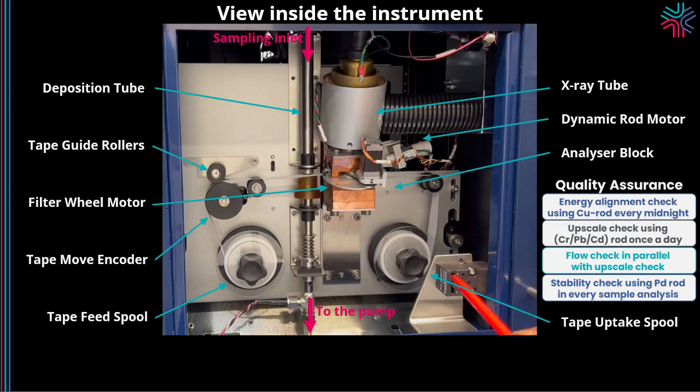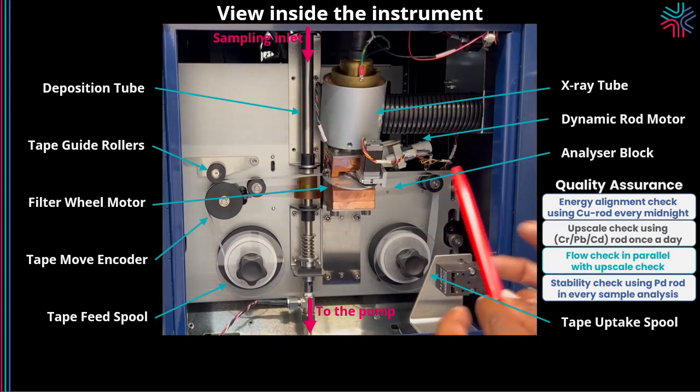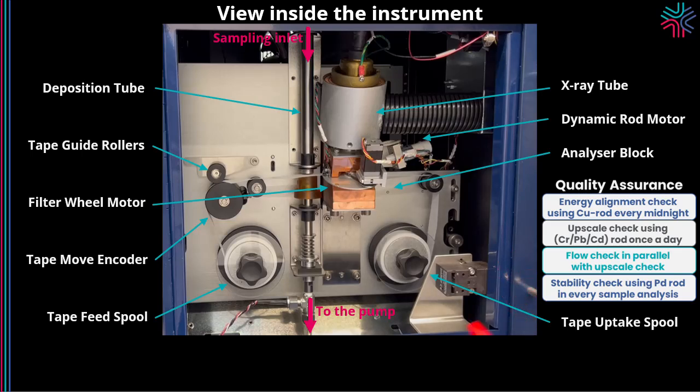One other important thing is that you have some sensors to protect you from the X-ray. So whenever the instrument is open, the door is open, these sensors are activated and the X-ray tube goes off. So that's a very good security measure that Cooper has done to safeguard the setup. Now we can look behind the instrument and try to start the measure.